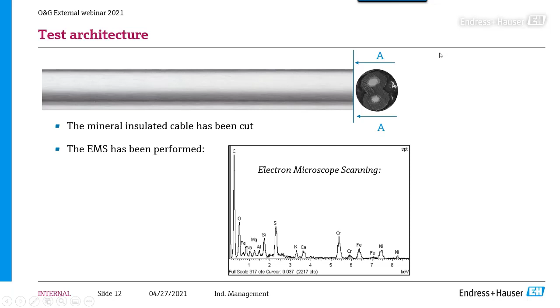Looking at the chemical composition of this area, area number 2, we find something interesting. Of course there's a lot of oxygen, which is obvious since the powder inside the thermocouple is magnesium oxide, so that's clear, and magnesium itself is no problem. Then we have a negligible quantity of aluminium and silicon. But we also find something unforeseeable: a very high content of sulfur. Then a low quantity of chromium, iron, and a lot of nickel. Basically, we should only have magnesium and oxygen here, but we also have nickel and sulfur.